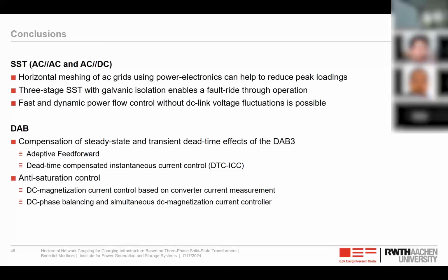And further, with this three-stage SST, so with a galvanic isolation stage, we can also enable a fault ride-through operation, because typically we want this kind of grid applications that we just put it there, and it can work autonomously for a long time without any disturbances.